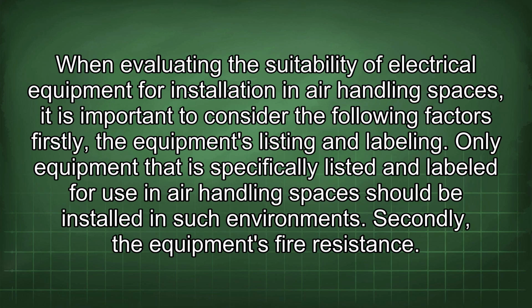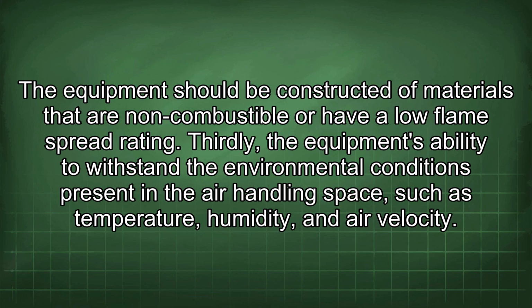When evaluating the suitability of electrical equipment for installation in air handling spaces, it is important to consider the following factors. Firstly, the equipment's listing and labeling. Only equipment that is specifically listed and labeled for use in air handling spaces should be installed in such environments. Secondly, the equipment's fire resistance. The equipment should be constructed of materials that are non-combustible or have a low flame spread rating. Thirdly, the equipment's ability to withstand the environmental conditions present in the air handling space, such as temperature, humidity, and air velocity.